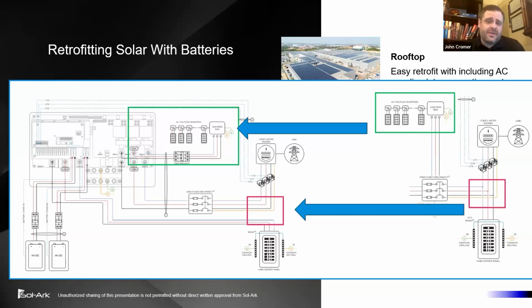The transformer conductors, the conductors that go out to the transformer, would now land on the grid port of the Sol-Ark. And then your conductors that go off to the building, you would land on the load port. So if you imagine a supply side tap that goes in line between the building meter and the main service panel, the Sol-Ark inverter has the ports needed to connect the AC coupled solar, the utility service, and the main service panel built into that inverter. So it can be a very quick and easy drop-in solution for adding batteries to existing solar arrays.